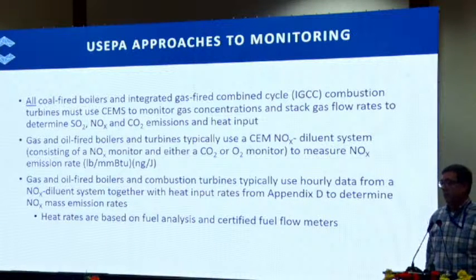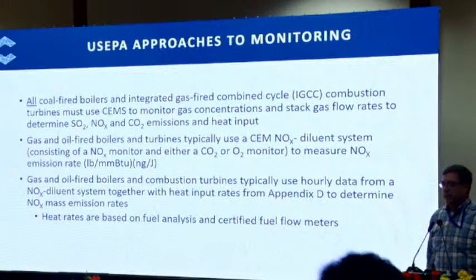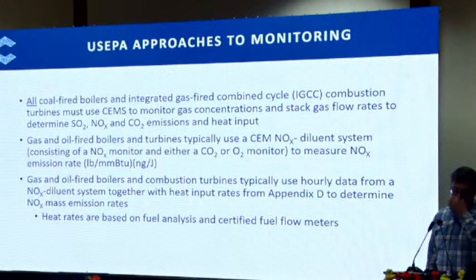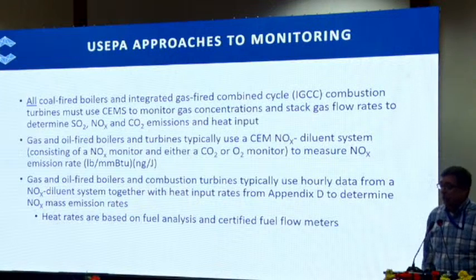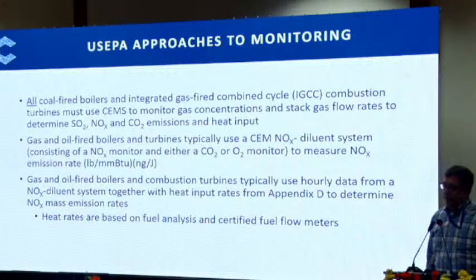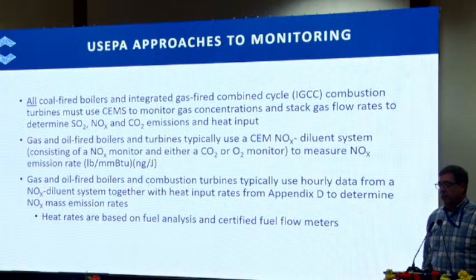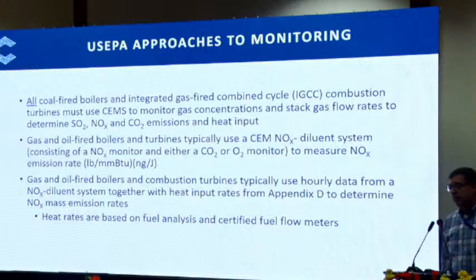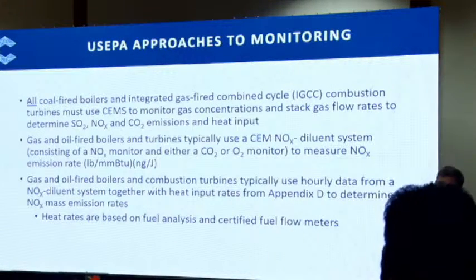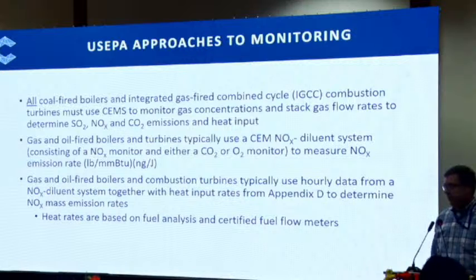Gas and oil-fired boilers and turbines typically use a NOx CEMS diluent system, which has CO2 or O2, to measure NOx emission rates. Gas and oil-fired boilers and combustion turbines typically use hourly data from a NOx diluent system together with heat input rates to determine NOx mass emission rates. Heat rates can be based on fuel analysis and certified flow meters.